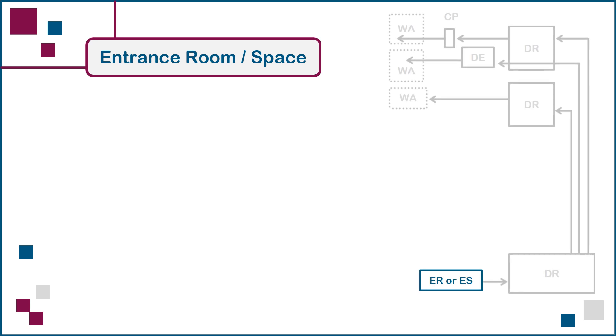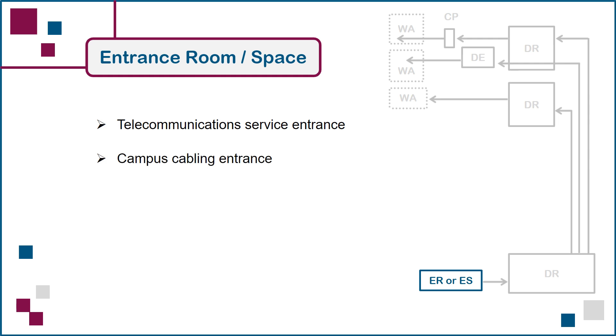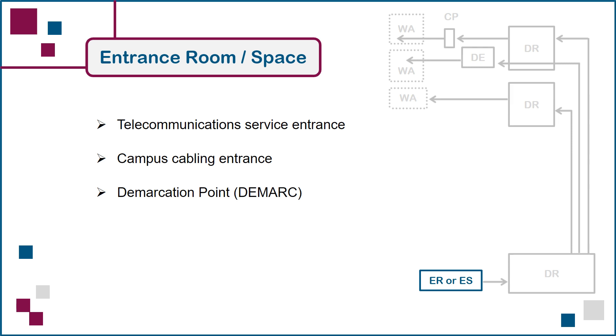In addition to cables providing telecommunications circuits to the building, any cables linking this building to one or more other buildings on a shared campus will also be terminated at this location. A term used here is demarcation point, or demarc, which indicates the exact spot where responsibility for the incoming telecommunications circuits passes from the circuit provider to the building owner. If there's a problem anywhere in the building with a circuit, the provider will test in the outward direction at the demarc. A successful test result will indicate that the problem is on the building owner's side and not the provider's responsibility.